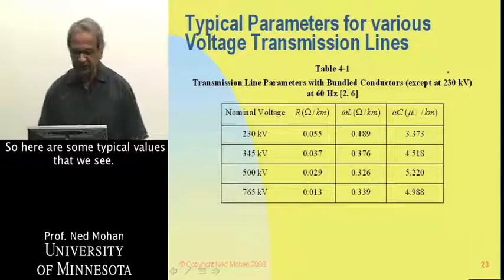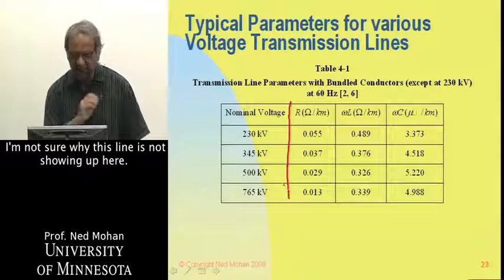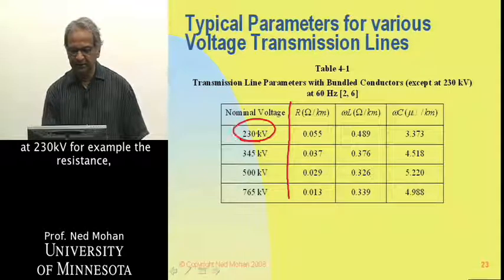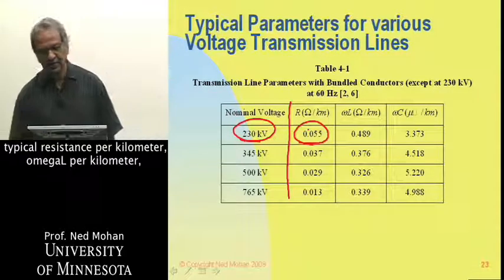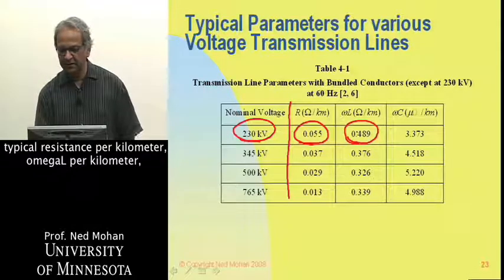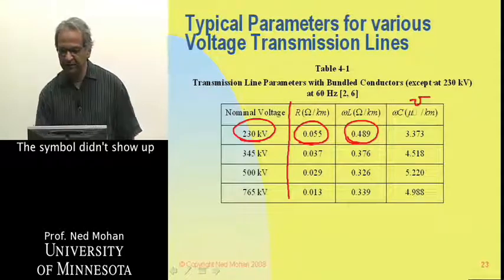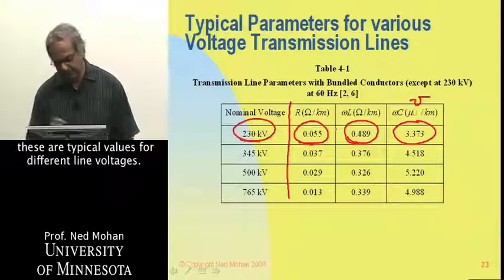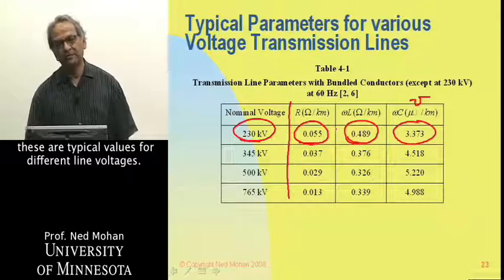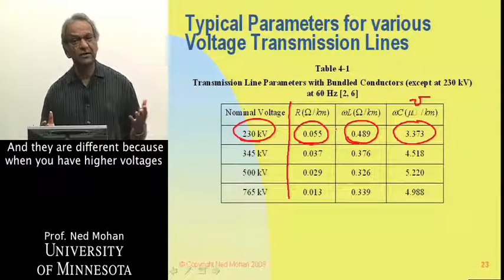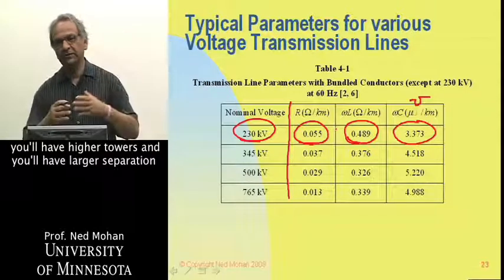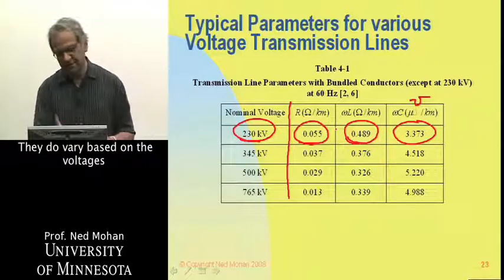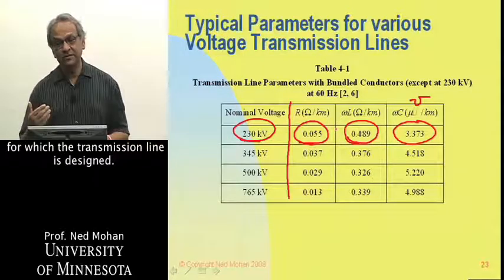So here are some typical values that we see. I'm not sure why this line is not showing up here. Let me just draw it. And it shows that at 230 kV, for example, the resistance, typical resistance per kilometer, omega L per kilometer, and omega C in micro-mhos, this symbol didn't show up, per kilometer over here, omega C here. Similarly, these are typical values for different line voltages. And they are different because when you have higher voltages, you will have higher towers, and you will have larger separation between the conductors. So these values are not constant. They do vary based on the voltages for which the transmission line is designed.